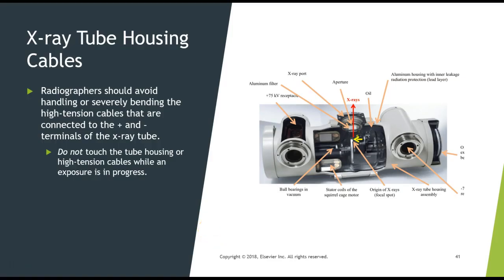Okay, moving on to other safety concerns. Radiographers should avoid handling or severely bending the high tension cables that are connected to the positive and negative terminals of the X-ray tube. And we've all done this. We've all been in an X-ray room where we have spun the tube around to accommodate our patient, and you end up getting all of those cables wrapped around the mounting pole or mounting housing. You need to watch that, okay?